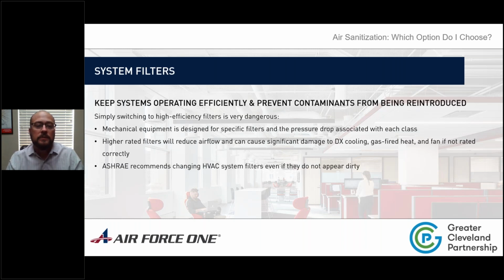The next important piece of this, and we've heard a lot about this, is system filters. There's been some kind of arguments on what you should do. And Air Force One is in agreement that you can install the highest rated filters for your system, but you need to know what that is. A lot of people are recommending HEPA filters or MERV 13 filters, which are great, but most HVAC systems are not designed to handle those filters. So simply switching to high efficiency filters can be very dangerous. Higher filters will reduce airflow and can cause significant damage.